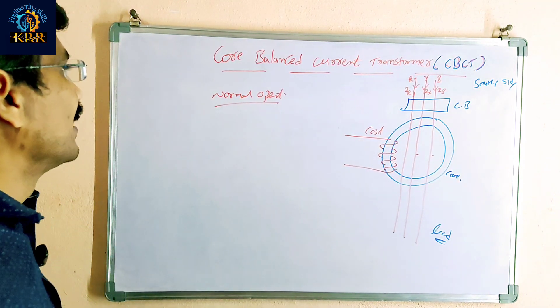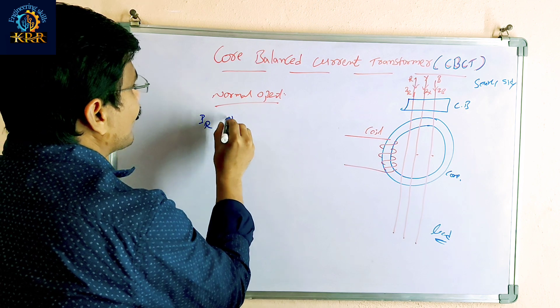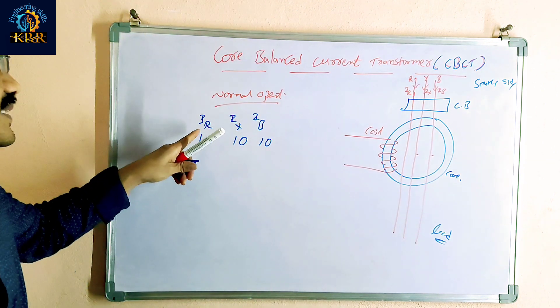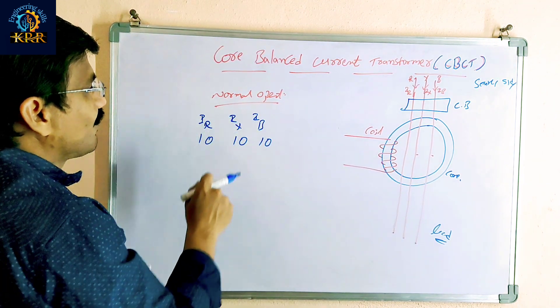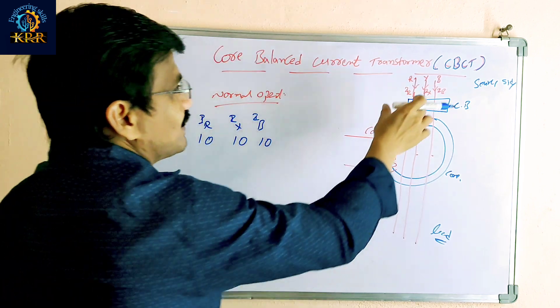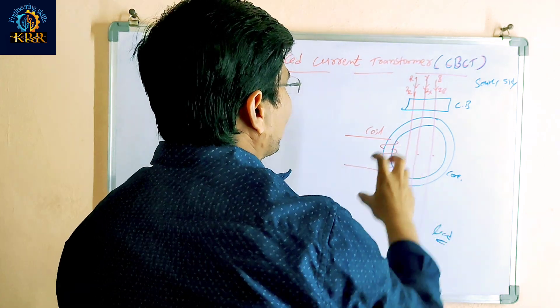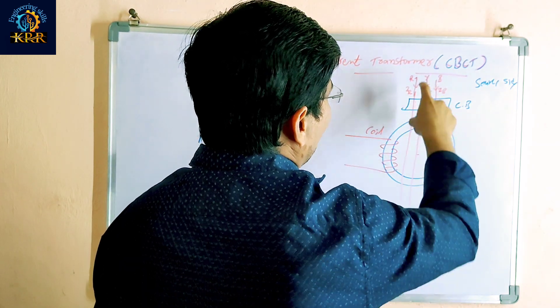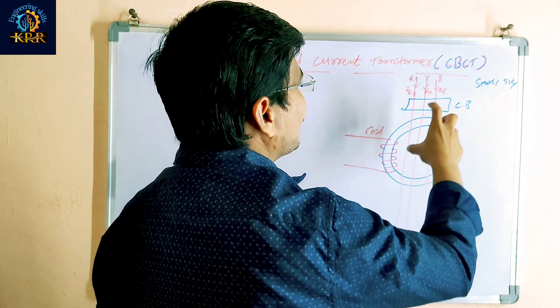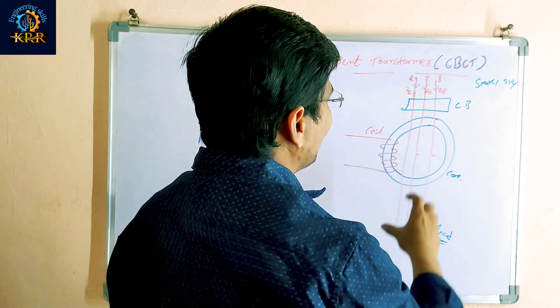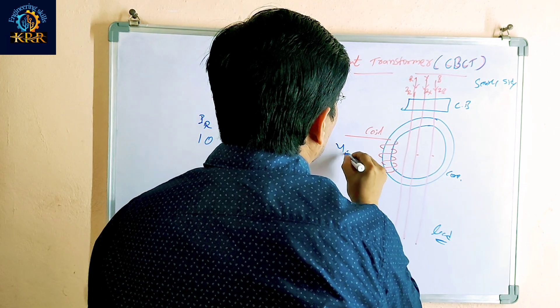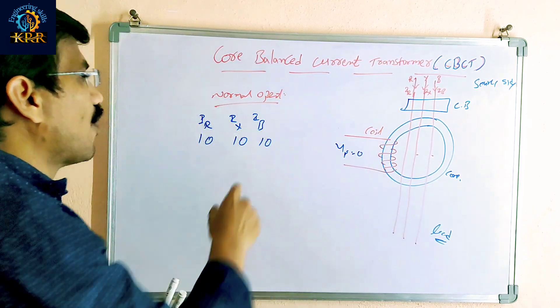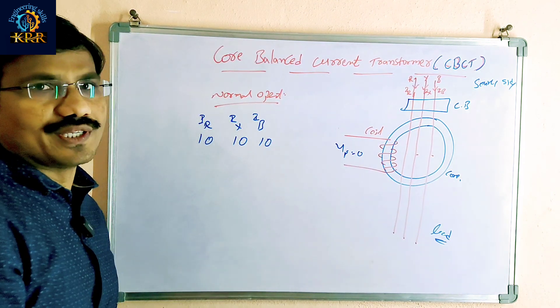In normal operation, IR = 10A, IY = 10A, IB = 10A. These three feeders carry 10A each. Each phase generates a corresponding flux. The resultant flux is zero, so the voltage at the coil is zero. Normal operation continues with no tripping.